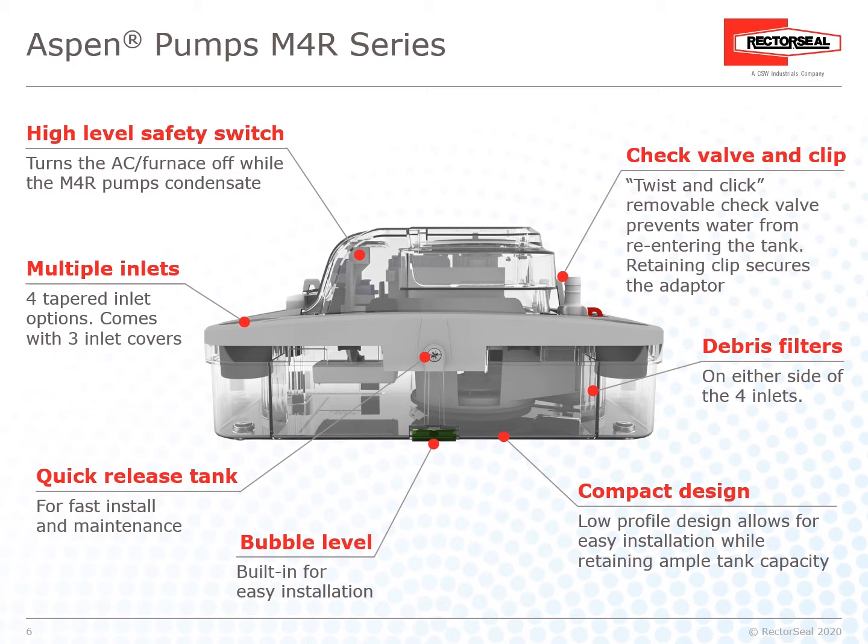The M4R includes a high-level safety switch that turns the AC or furnace off while the pump removes condensate. It has four tapered inlet options and comes with three inlet covers. A quick-release tank allows faster install and maintenance. A built-in bubble level aids easy installation. The twist-and-click removable check valve prevents water from re-entering the tank, and a retaining clip secures the adapter. Debris filters are located on either side of the four inlets. The low-profile design allows for easy installation while retaining ample tank capacity.